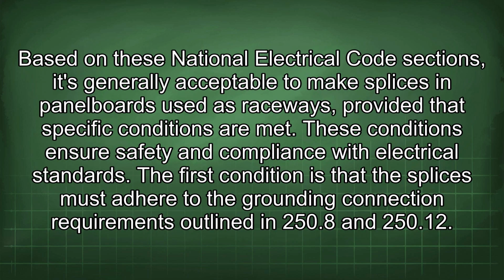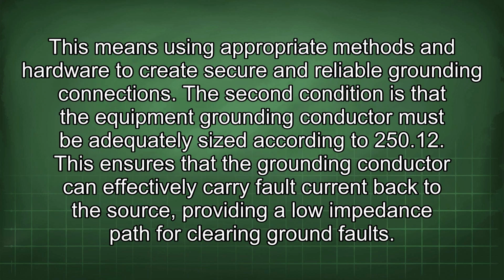Based on these National Electrical Code sections, it's generally acceptable to make splices in panelboards used as raceways, provided that specific conditions are met. These conditions ensure safety and compliance with electrical standards. The first condition is that the splices must adhere to the grounding connection requirements outlined in 250.8 and 250.12. This means using appropriate methods and hardware to create secure and reliable grounding connections.